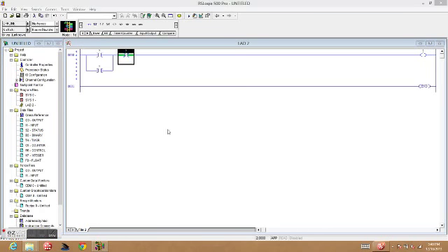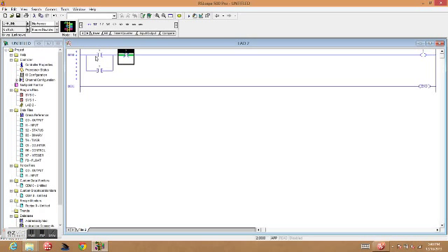The idea behind this program is that you have a stop button, start button, and a coil, which is the motor. So what happens is you tap the start button, and that closes the contact, lets energy all the way through to the coil. Now this is where it gets fun. The coil, when it gets energized, also energizes this contact, which is connected to the coil. So what happens is the coil gets energized, this contact closes, so you can then release the start button, open it back up, and the energy will travel down through here, through that closed contact that's connected to the coil, go back here, and back through the coil. So now the coil is stuck on even though you've let go of the start button. Then you can just press the stop button, open this up, cut off energy, and turn everything back off.